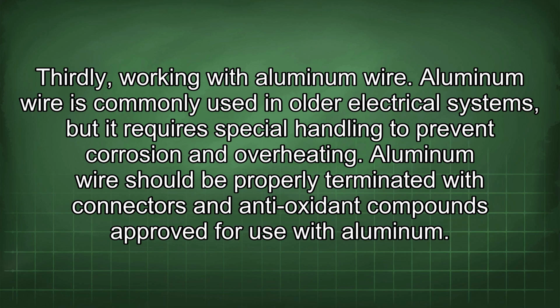Thirdly, working with aluminum wire. Aluminum wire is commonly used in older electrical systems, but it requires special handling to prevent corrosion and overheating. Aluminum wire should be properly terminated with connectors and antioxidant compounds approved for use with aluminum.